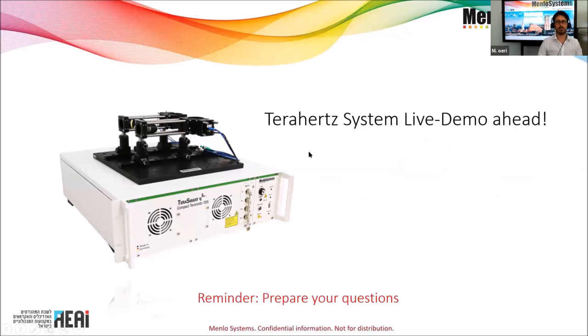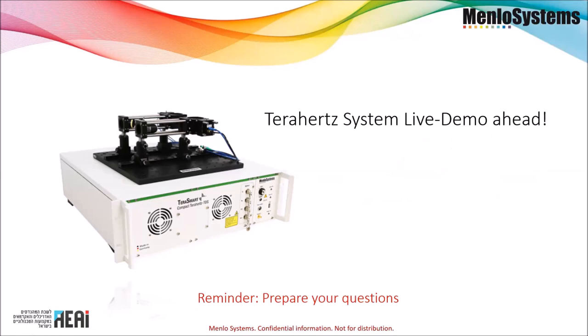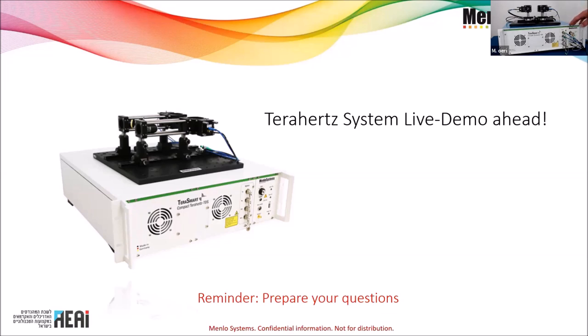Now let's move to the live terahertz system demo. The system is running and I'd like to give a short introduction of its components. Inside the 19-inch rack there is a laser source sitting behind a cooling fan — it needs no water cooling. We have the optical unit with access for transport. When moving the system to a different location, the only external connection needed is the power supply. You would also fix the optical delay unit to prevent movement during transport.